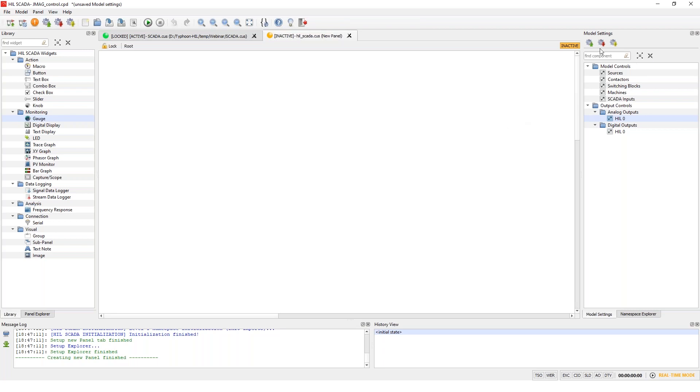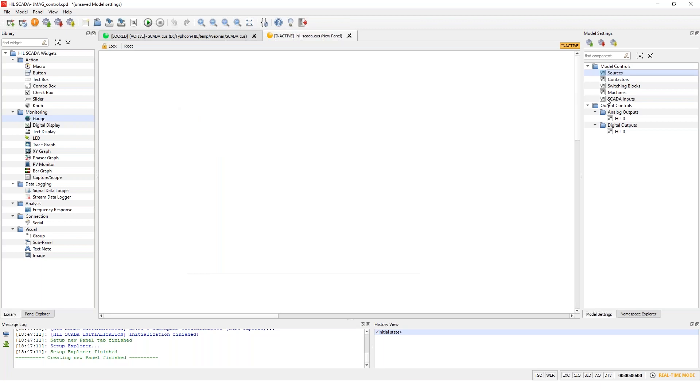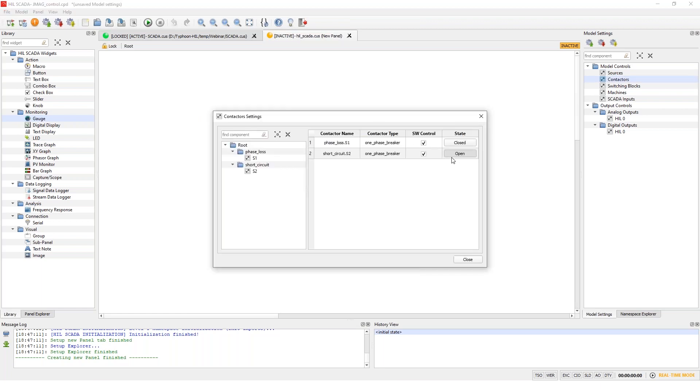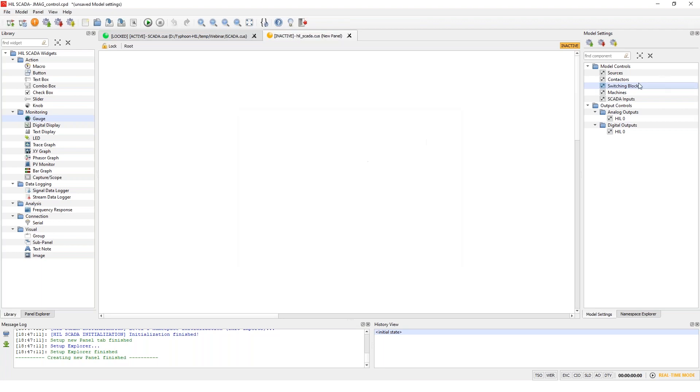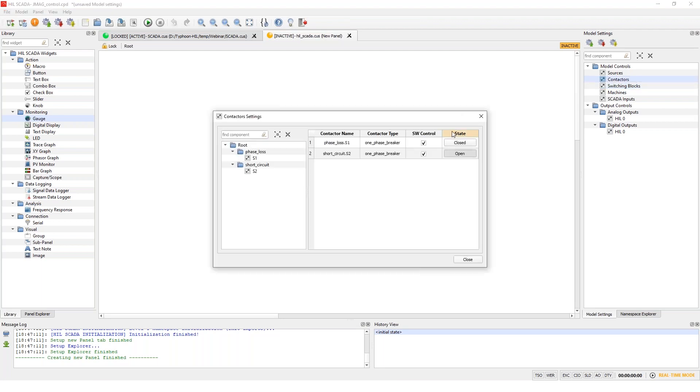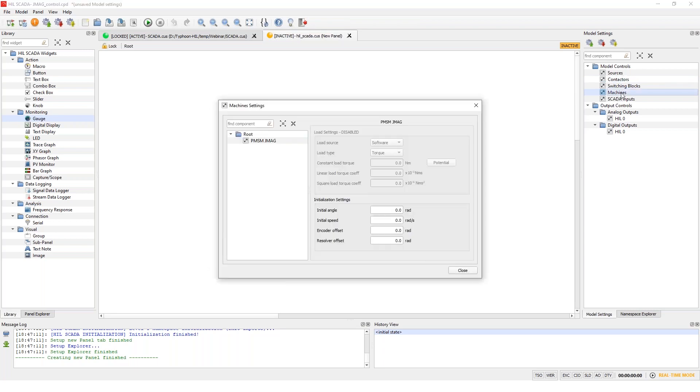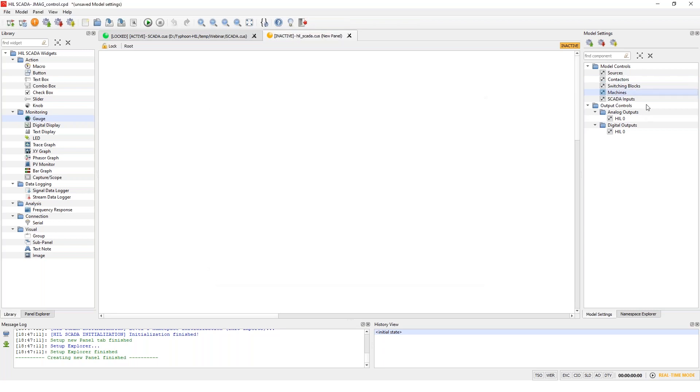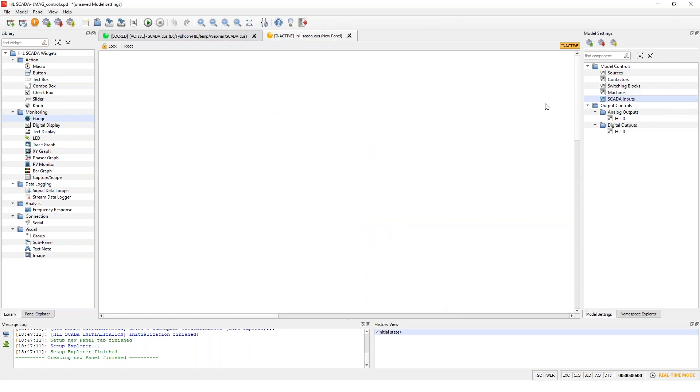So you have an empty panel, which you can populate with the widgets from the left to make a custom user interface that will allow you to control the simulation to introduce disturbances to the system and also to observe what's going on in the system. Then first here on the right, in the right part, we have these buttons under model controls. So these allow us to set, for example, the voltages of the voltage sources in the simulation, we can override the contactor and switches gating signals. So we can force them to be always on or always off. That's how we actually simulate the faults. In this demo, then we can set some initial conditions for the machine models.